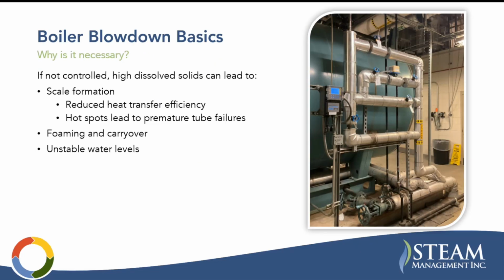Why is it necessary to remove dissolved solids or solids in general? If not controlled, high dissolved solids can lead to scale formation, which can reduce heat transfer efficiency, lead to hot spots, and premature tube failures. Basically, scale is going to insulate your boiler tubes, and even a 1/16 of an inch of scale can increase your tube wall temperatures by hundreds of degrees. So it's making a big difference in the lifespan of your boiler tubes, as well as your thermal efficiency.